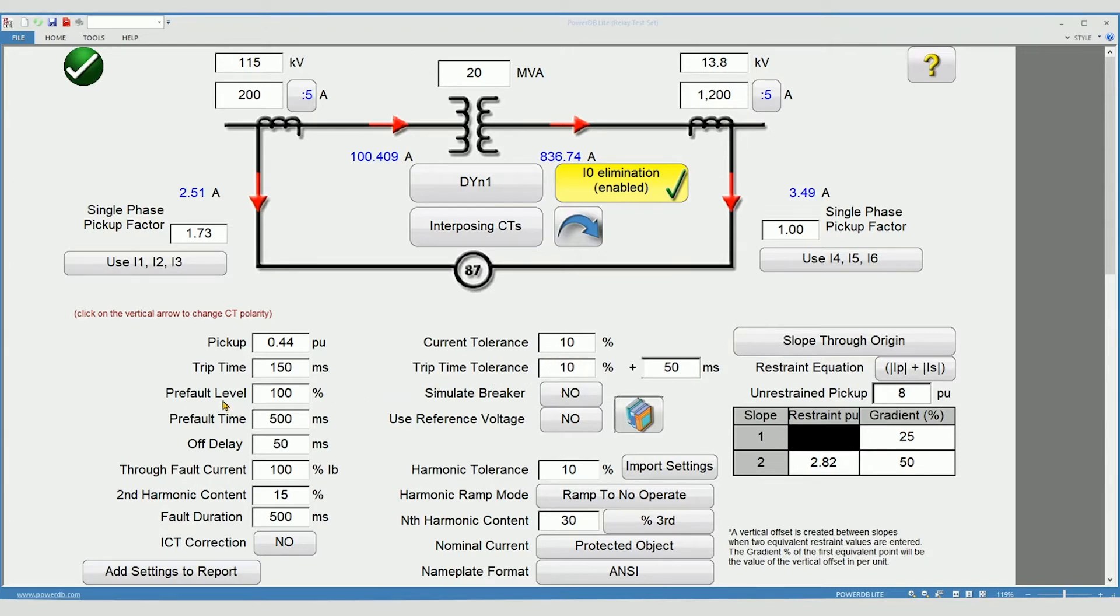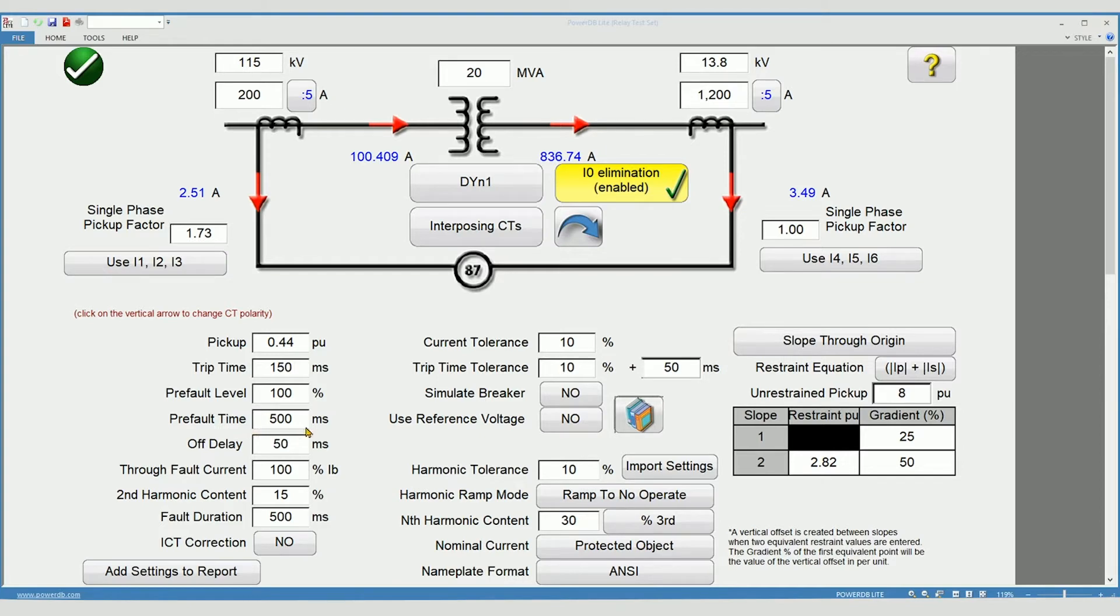Prefault level determines the amount of load current to be applied to the relay prior to simulating a fault. Prefault time determines how long the prefault will be applied before executing the test.